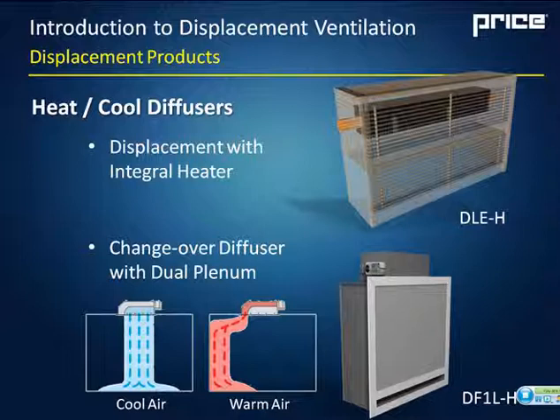Once it's into heating mode, it gets a signal from either the BAS or the building controls that tells it that it's into heating mode, to switch over that actuator, close off the cooling plenum and open up the heating plenum, which is now going to direct all the warm air through that slot diffuser on the bottom. So that slot diffuser has a pattern control so that you can adjust it for a horizontal pattern or vertical pattern, so you can condition a window or a wall or something like that.